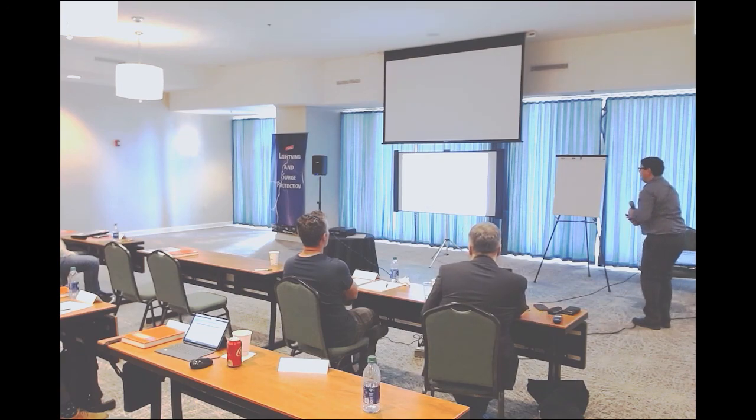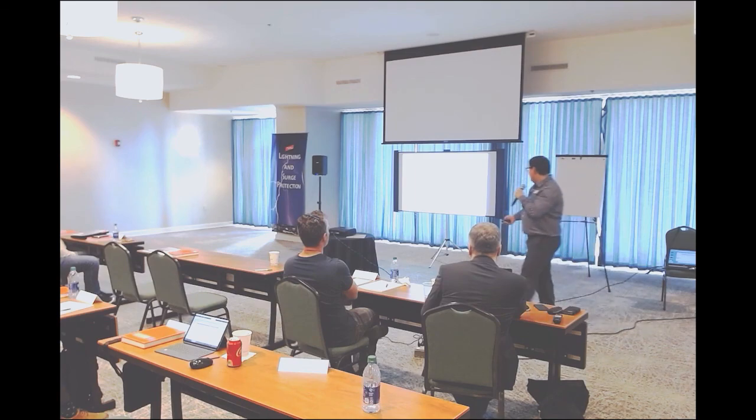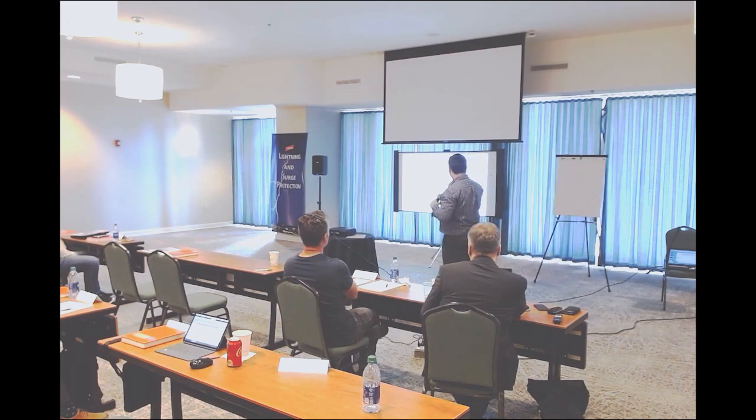Yeah, I know client information is there, but it's fine. I want to show you. So that is the design. And you can see there you have EX zones and everything over here. That's why we had air termination rods that were tips up 1 meter outside of the EX zones.